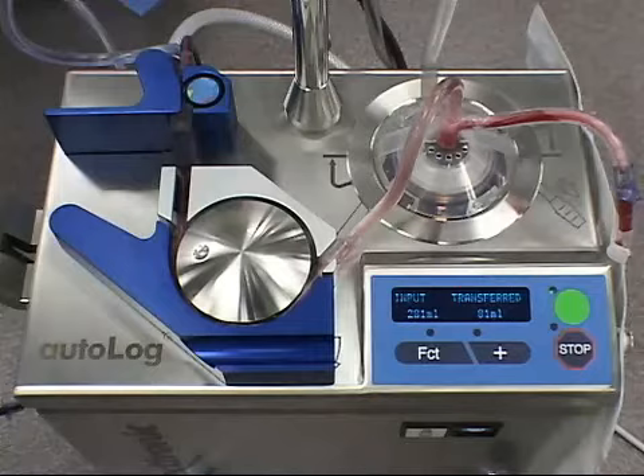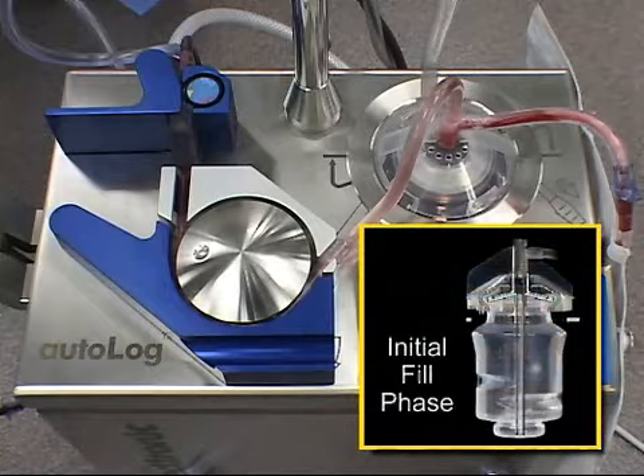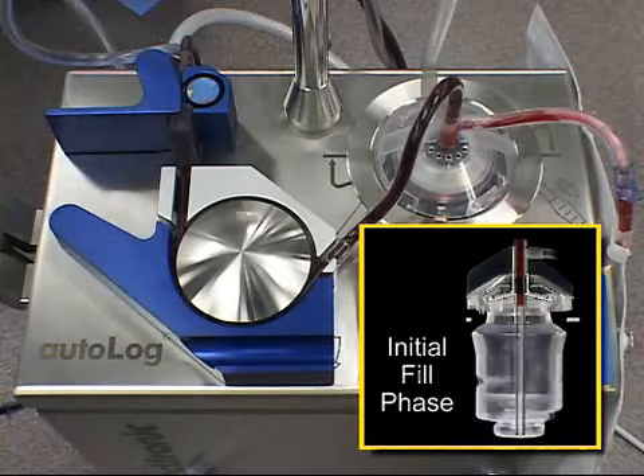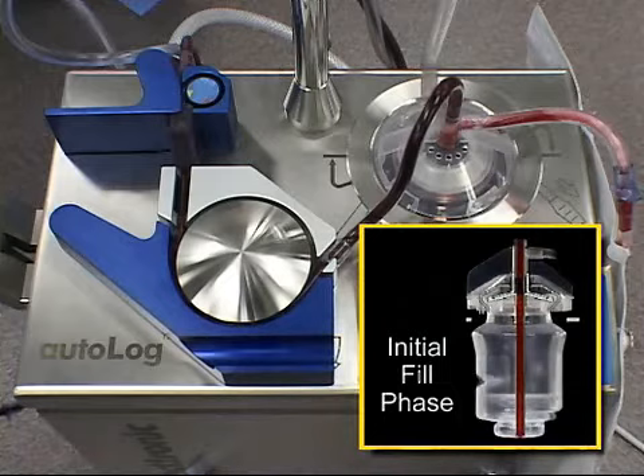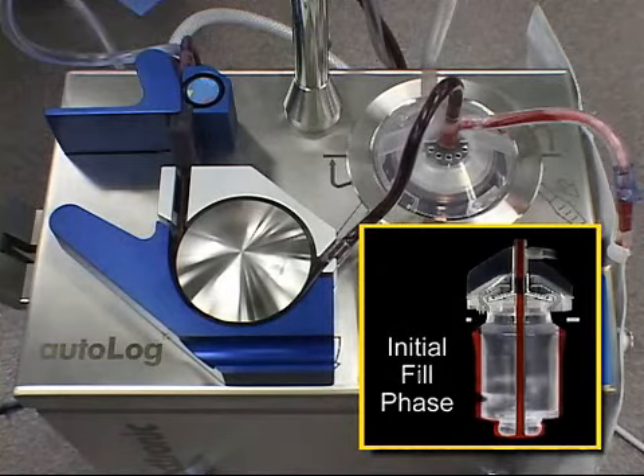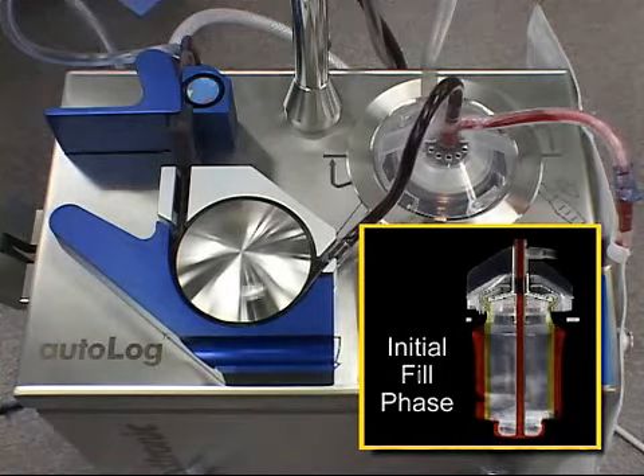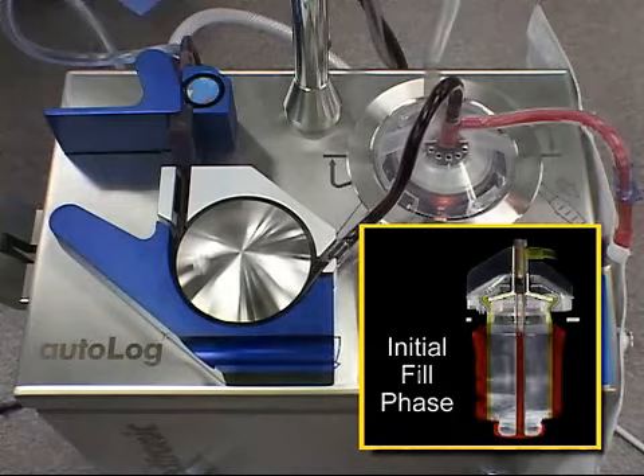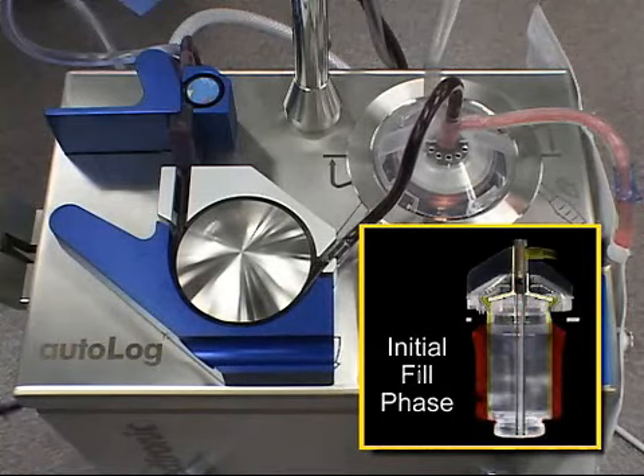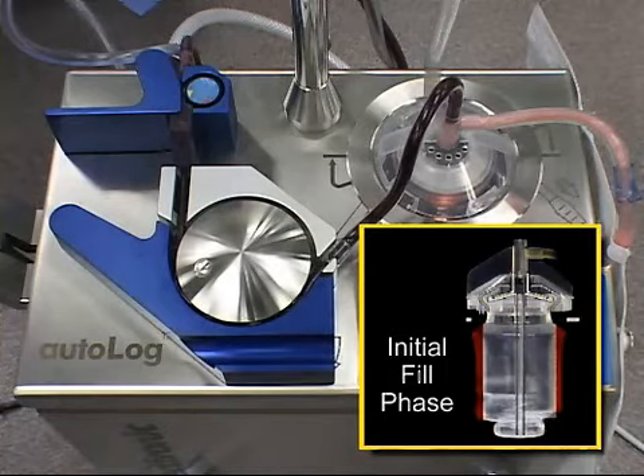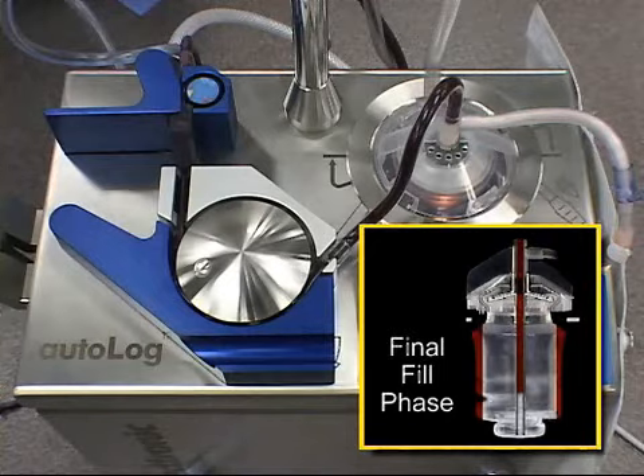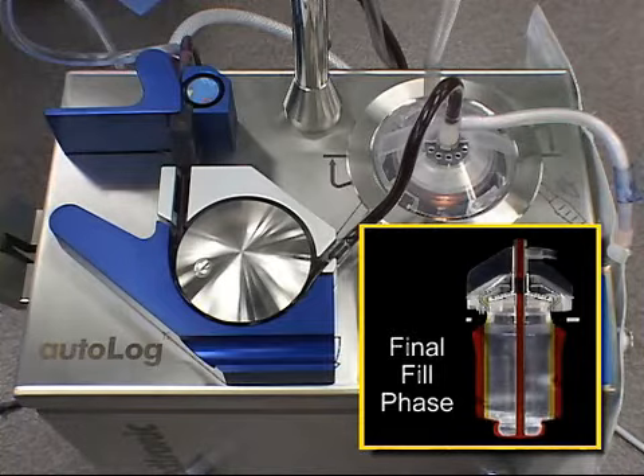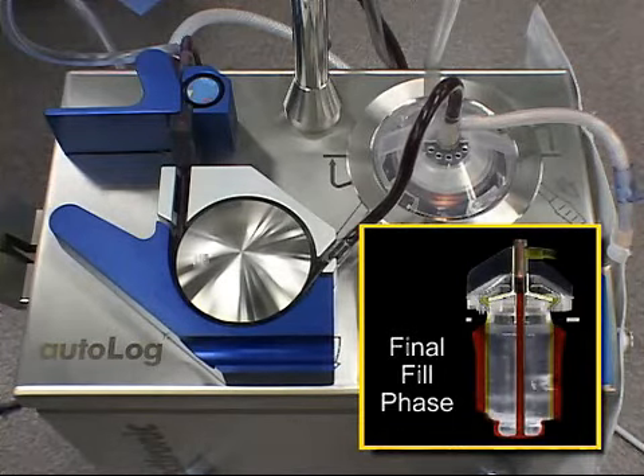The AutoLog employs an innovative 2-stage centrifuge bowl filling. In the initial fill phase, the AutoLog centrifuge and fluid pump will rotate and the bowl will fill at a rate of approximately 600 milliliters per minute. The pump momentarily stops after the initial detection of red blood cells. The final filling stage, initiated after red blood cells pack against the sides of the bowl, will be either 250 or 600 milliliters per minute, based on the hematocrit of the incoming blood.